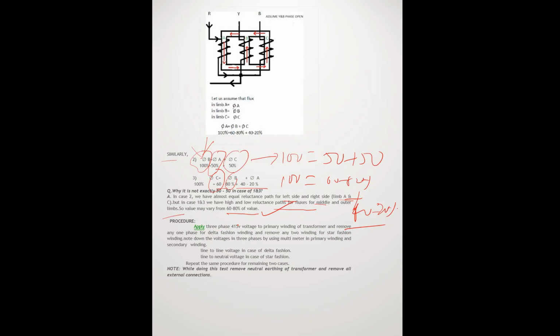And the procedure: apply three-phase 415 volt to the primary winding of the transformer, and remove any one phase for delta winding and remove any two phases for star winding. Note down the voltage in three phases by using a multimeter in the primary winding and secondary winding. Now this is the main important point. Line to line voltage is applied in the case of delta, because in delta there is no neutral point, but in the case of star, line to neutral voltage is applied. So repeat the same procedure for the remaining two cases. While doing this test, remove the neutral earthing of the transformer and remove all its external connections.